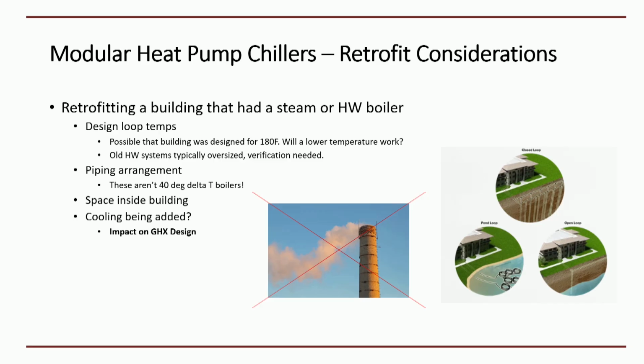Especially in the K through 12 market, we're seeing more and more where maybe a building is heating only now, and now you want to add cooling. That's very important to know up front, and that's going to fall right into this 6-pipe story, because we do want to take advantage of that simultaneous heating and cooling. But why that's so important is we want to make sure that ground heat exchanger is sized to handle both of those loads. We've been through enough of these where an imbalance is not going to be good. It's not going to equal good longevity for the system. So again, just tying that whole story together, we want to always pay attention to all of that.